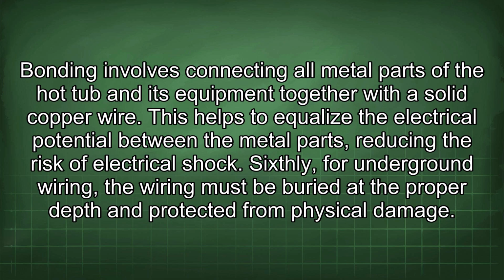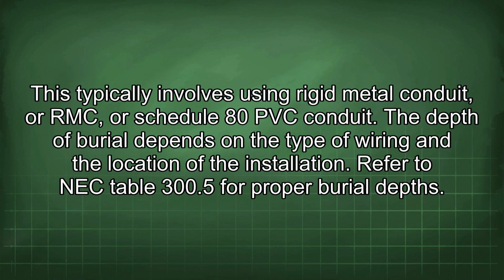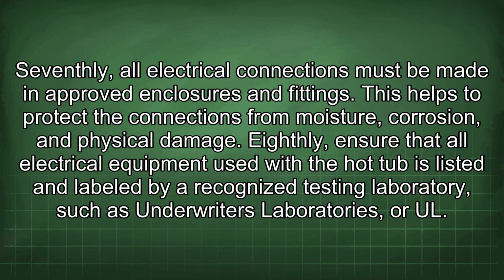Sixthly, for underground wiring, the wiring must be buried at the proper depth and protected from physical damage. This typically involves using rigid metal conduit, or RMC, or Schedule 80 PVC conduit. The depth of burial depends on the type of wiring and the location of the installation. Refer to NEC Table 300.5 for proper burial depths. Seventhly, all electrical connections must be made in approved enclosures and fittings. This helps to protect the connections from moisture, corrosion, and physical damage.